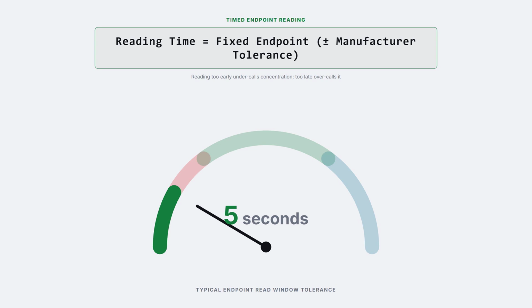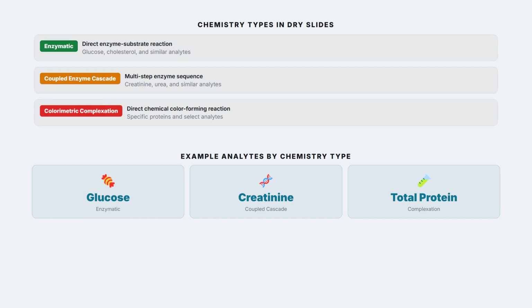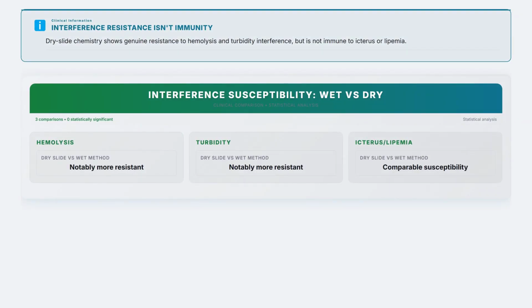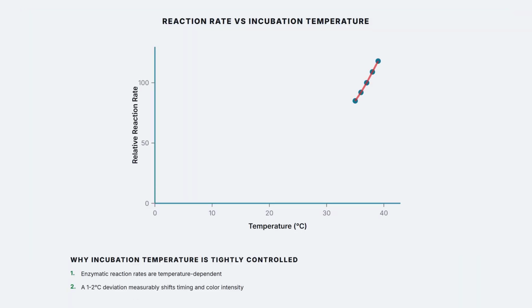The chemistry types packed into these reagent layers span the same breadth as wet chemistry, just reformatted for a solid phase format. Enzymatic reactions for glucose and cholesterol, coupled enzyme cascades for creatinine and urea, and colorimetric complexation reactions for electrolyte-adjacent analytes and specific proteins. One genuine chemistry-level advantage worth naming directly: because the spreading layer physically filters out cells and larger interfering particles, and because the reaction occurs in a thin, controlled film rather than a bulk liquid, dry slide chemistry shows real, documented resistance to hemolysis and turbidity interference compared to equivalent wet methods, though it is not immune to icterus or lipemia entirely. Temperature control during the reaction itself is handled by the instrument's incubation block, not the slide, and it's tightly regulated for exactly the same reason it matters in wet chemistry.